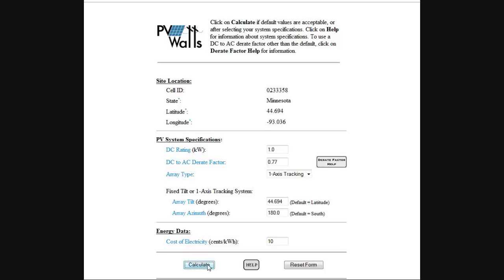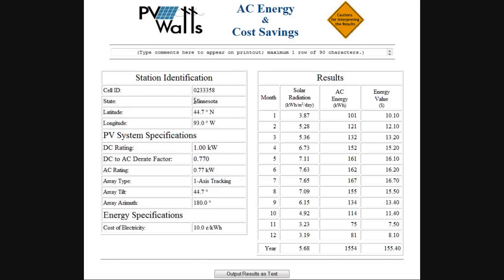Going back and switching to a single-axis tracking system and recalculating, the total for the year is now 1,554 kilowatt hours, up from 1,224. That's a 27% increase — so I would get a 27% annual increase just by adding single-axis tracking to my system.